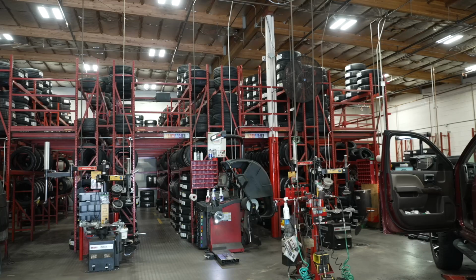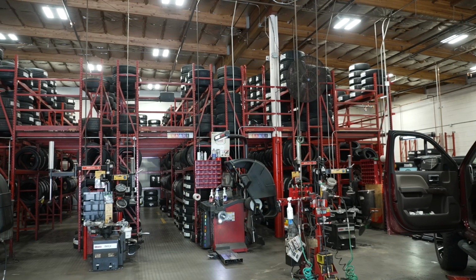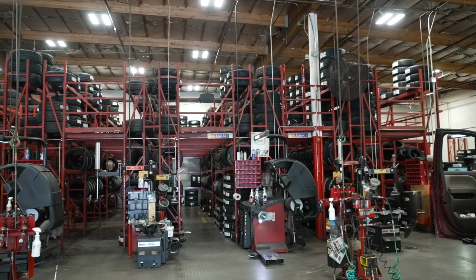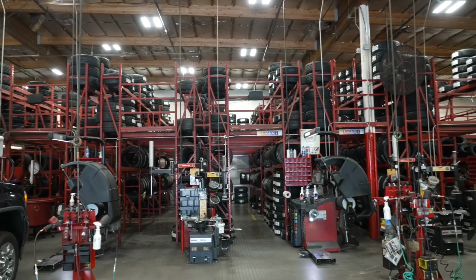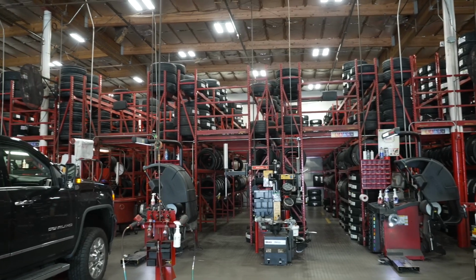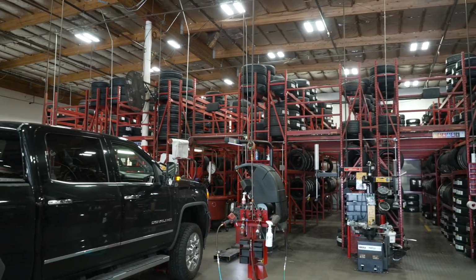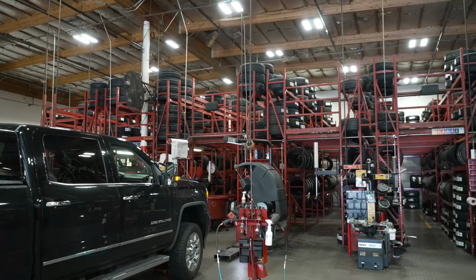Also in mercantile occupancies, we have tire storage that may be on 2 tiers. You may have an upper and a lower tier, and they still may be meeting the 6-foot height requirement, but in some cases they may get a little overzealous and go higher. So this is something we want to maintain fire code compliance with when we're doing our inspections.